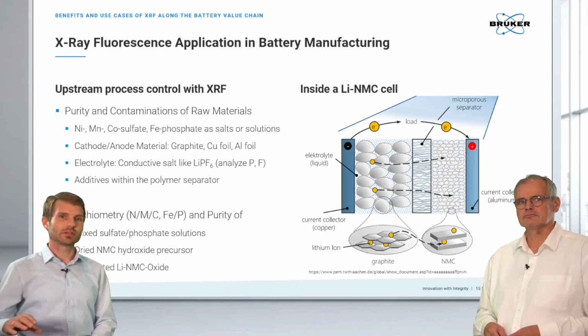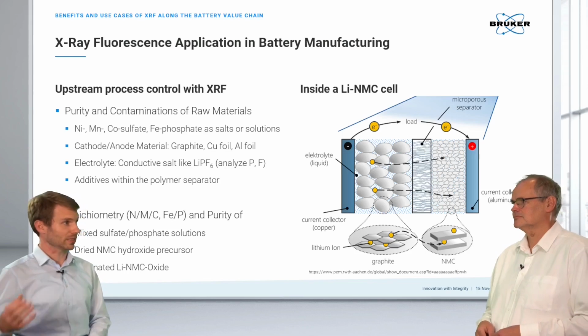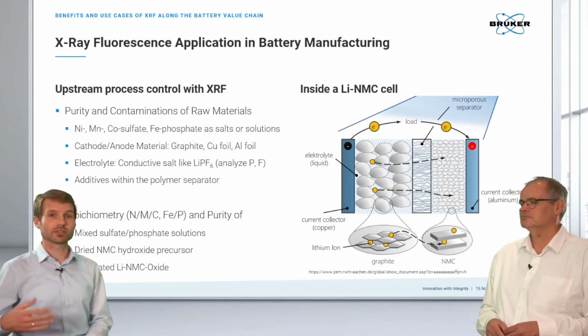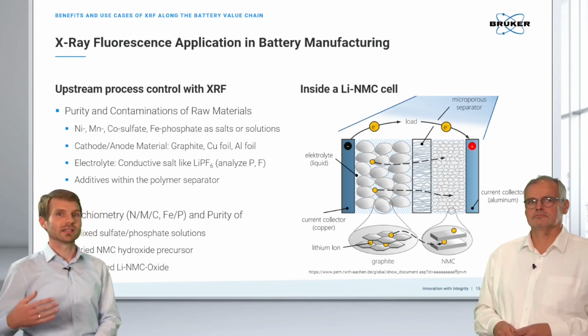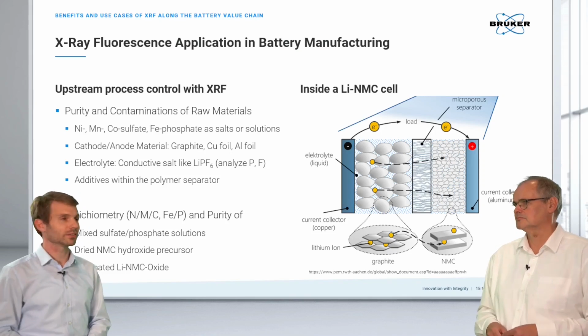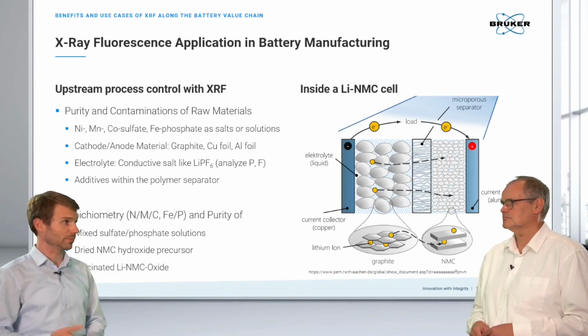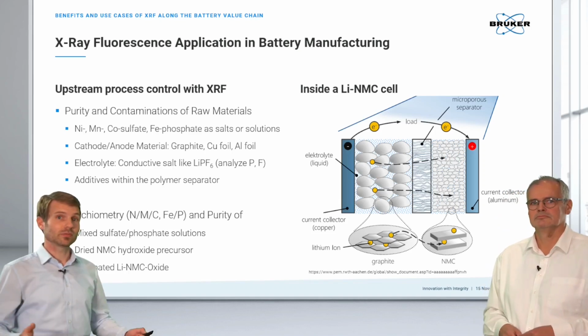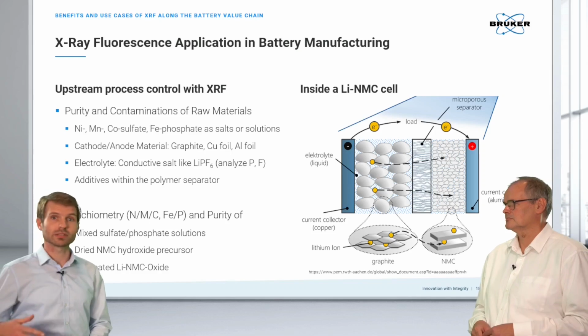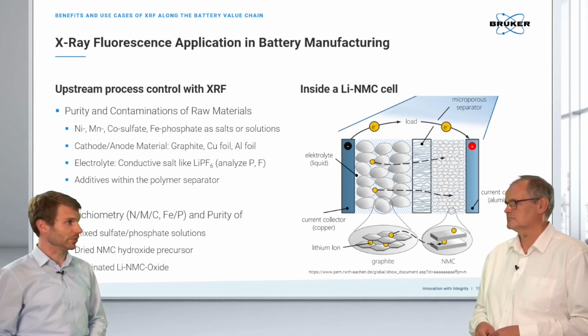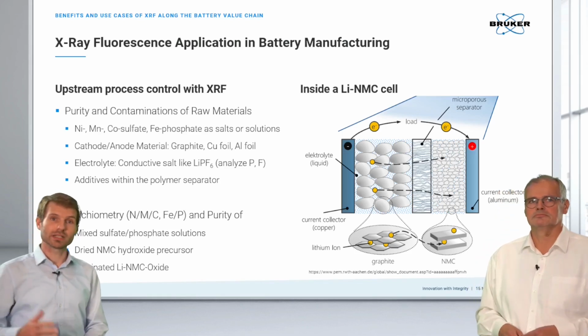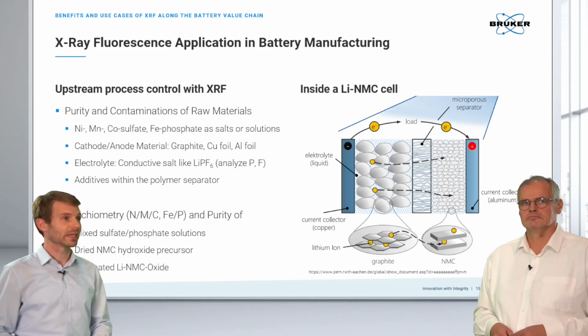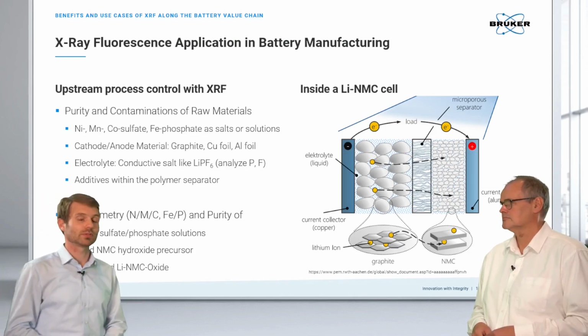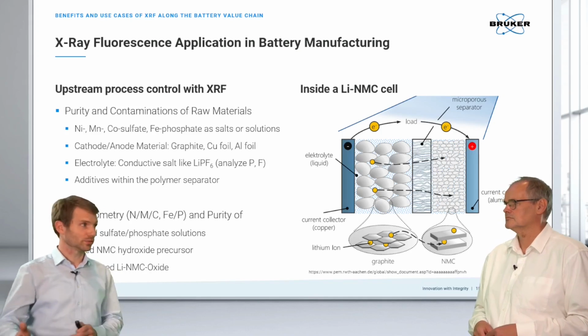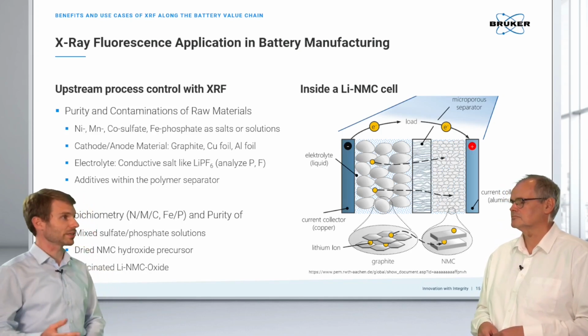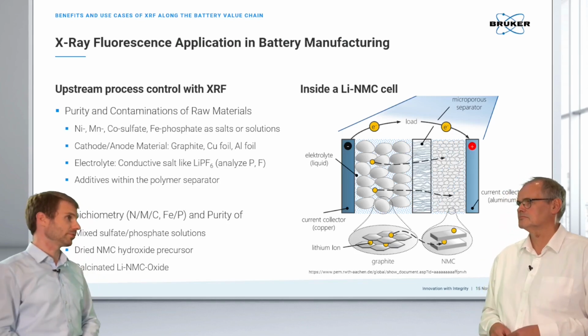So some of the most important ones are checking your raw materials. So this can be checking your nickel sulfate in terms of purity, but also making sure that it is actually nickel sulfate, or your cobalt sulfate, iron phosphate. These can all be easily checked in a liquid cup with the push of a button. Then we will look into cathode materials, anode materials like graphite, copper foil, aluminum foil. This can also be done by XRF to verify and get an idea about the potential contamination. And later on in the process, when we really produce the cathode active material, we are looking into stoichiometries and once again purity, so something that might come from the raw material or might come from the production process.